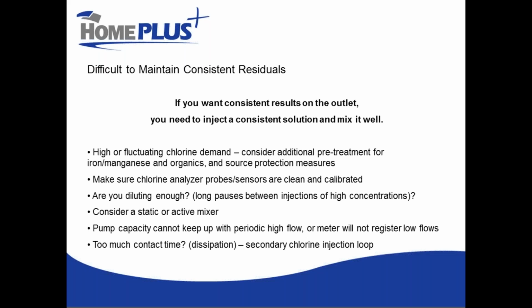Again, consider whether or not you're diluting appropriately, because those long pauses between injections can throw off our consistency. You can consider adding a mixer to improve that mixing. And also consider where you're measuring from as well, and how it relates to the mixing. If you're measuring your concentration in between your chlorine pump and your contact tank, don't expect a high level of consistency at that point, especially if you're measuring really close to your injection point.